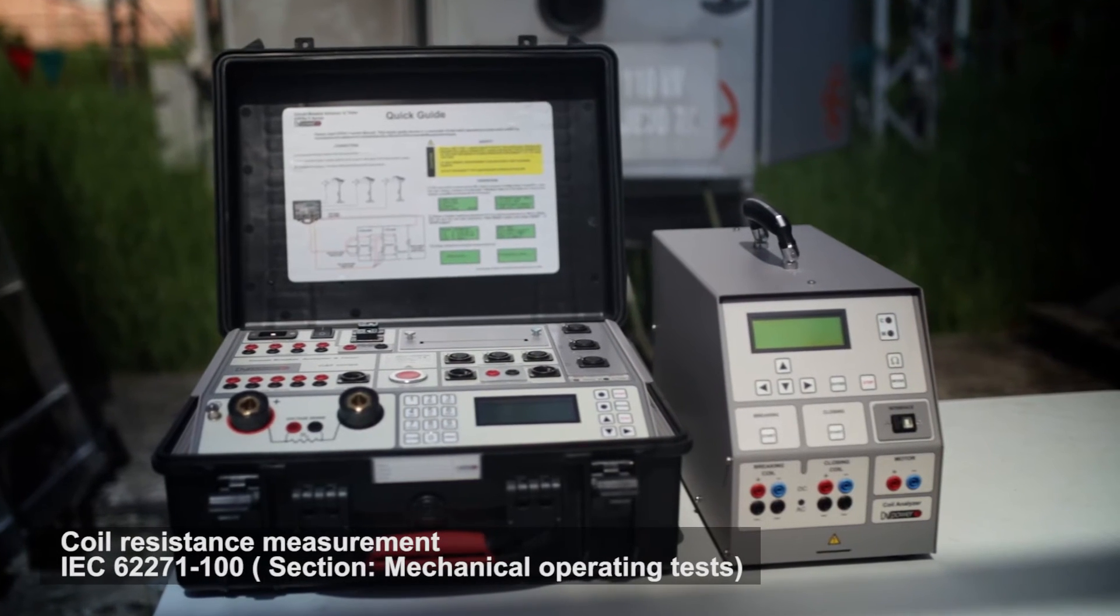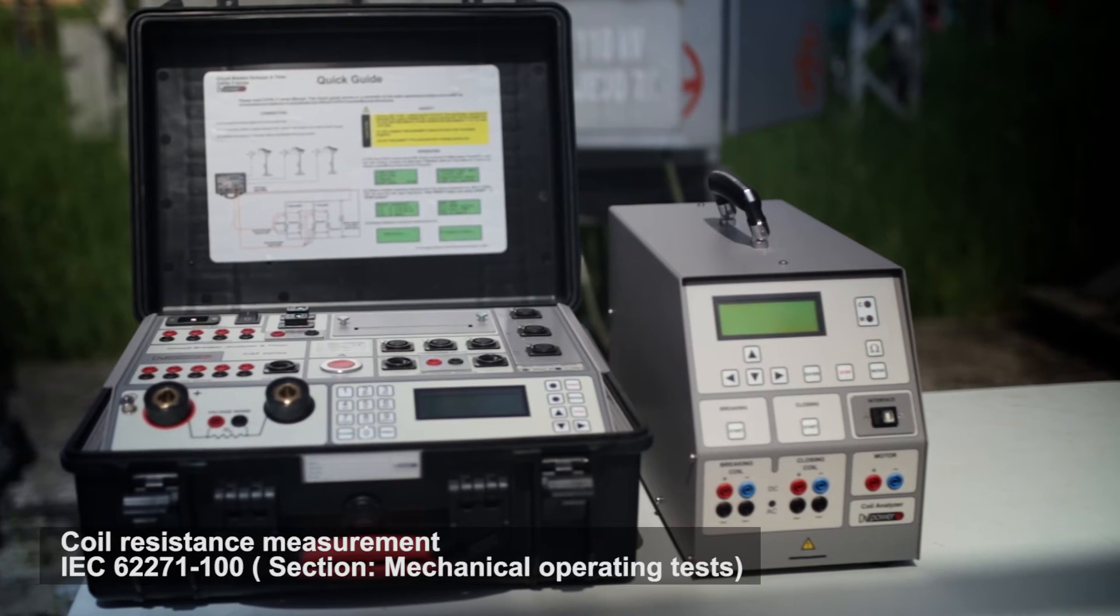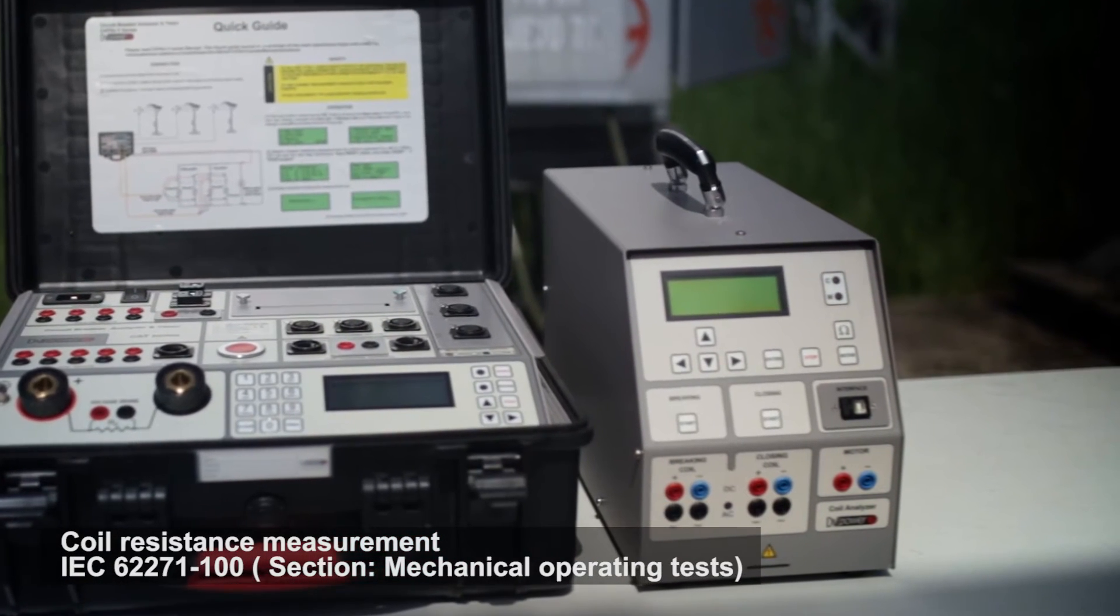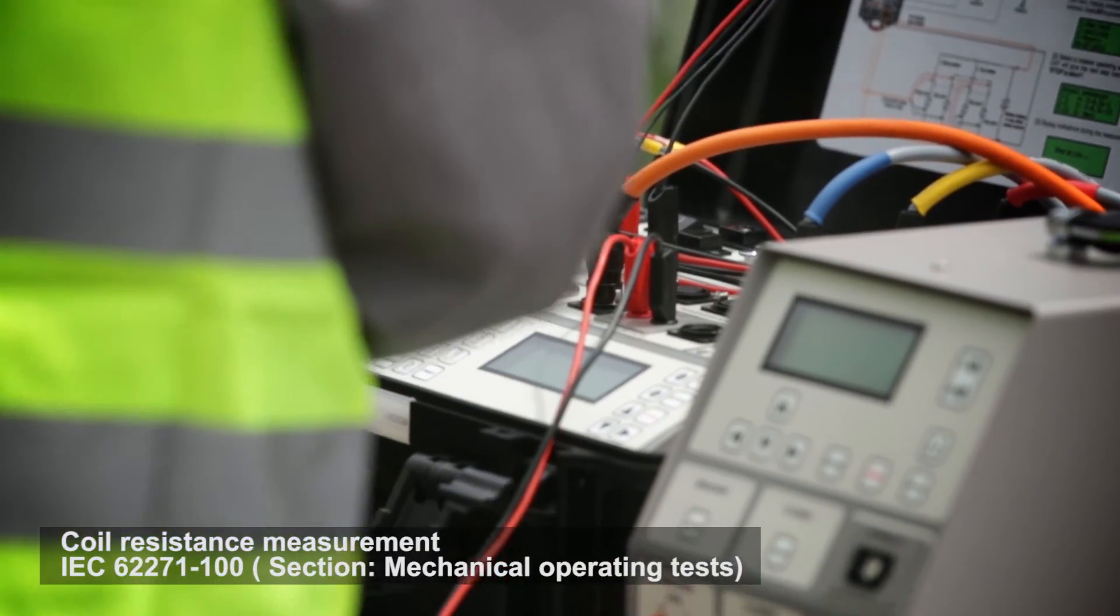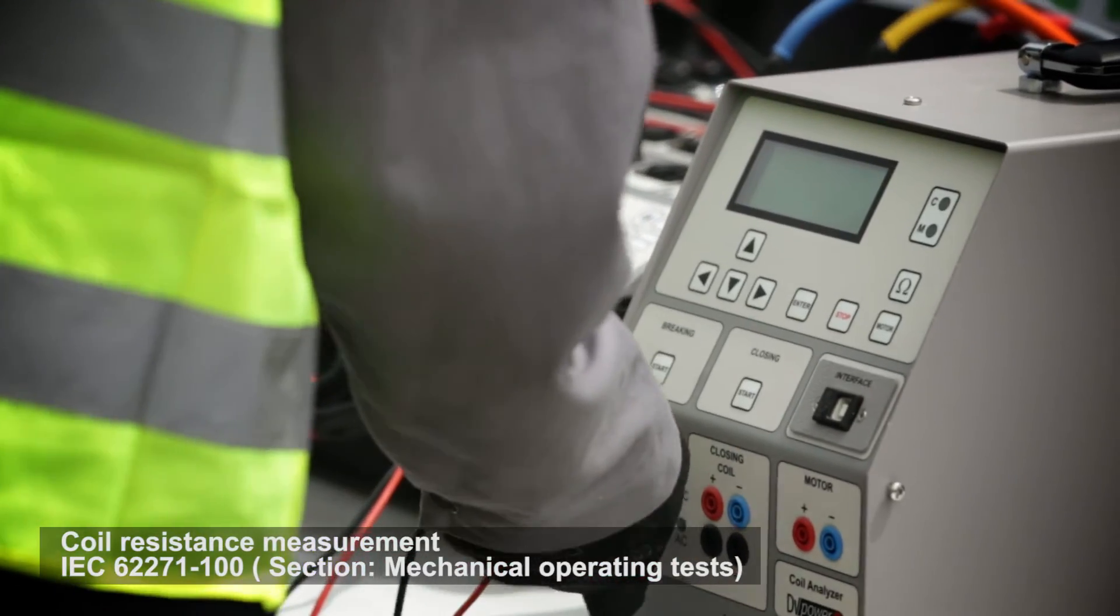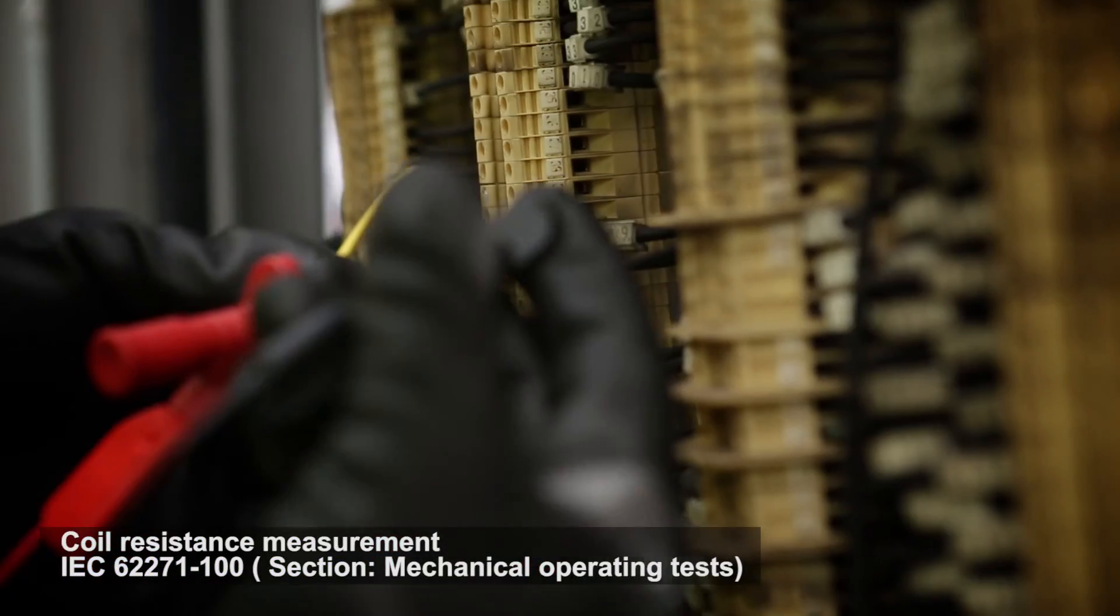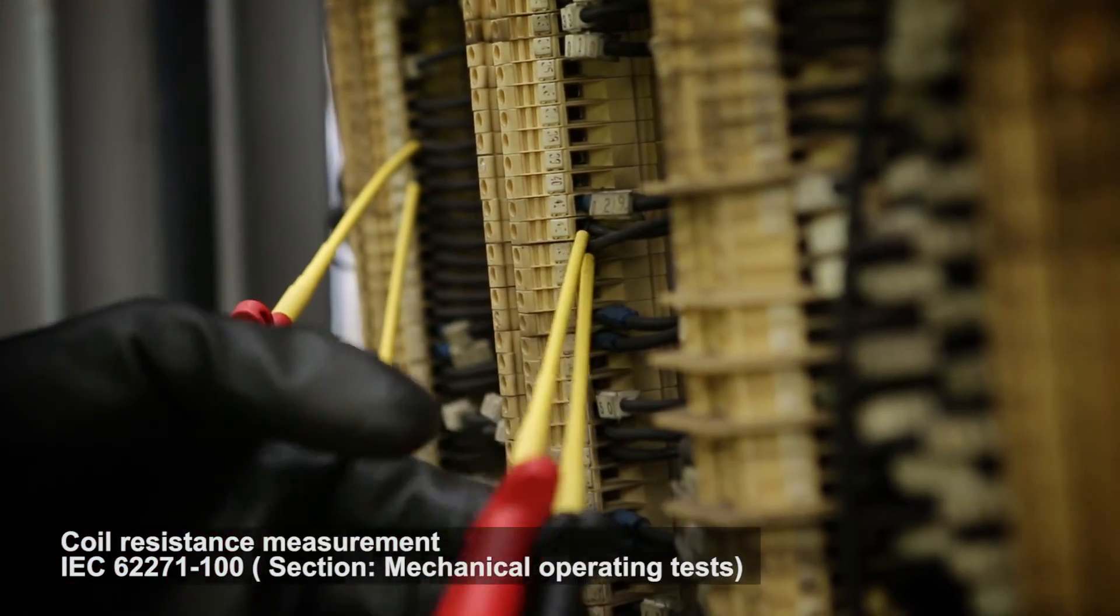The SAT instrument can measure the trip and close coil resistances. Its measurement procedure generates a very low current through the coil, which would not heat up the coil and consequently increase its resistance. The corresponding voltage drop is measured across the coil and used to calculate resistance according to Ohm's law.